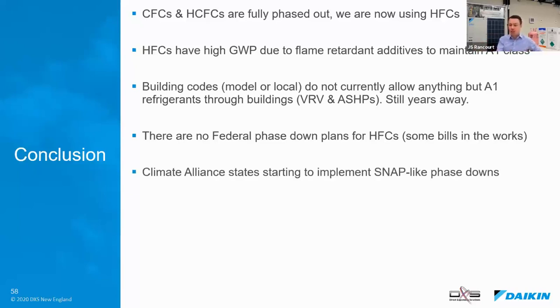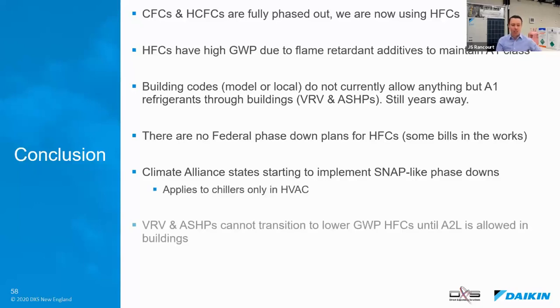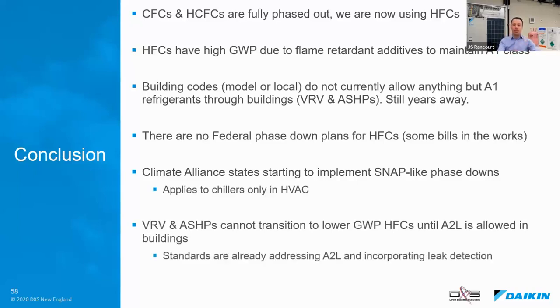It refers to SNAP. It applies to chillers only. VRV and air source heat pumps cannot transition to lower GWP until A2L is allowed in buildings. And R32 is the go-to refrigerant with the lowest life cycle climate performance impact on the equipment.